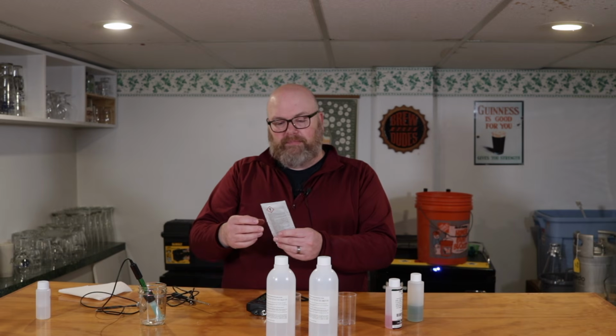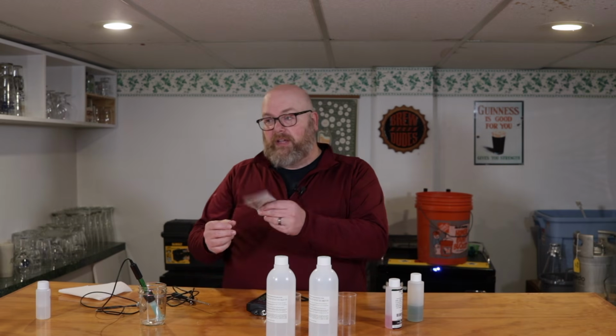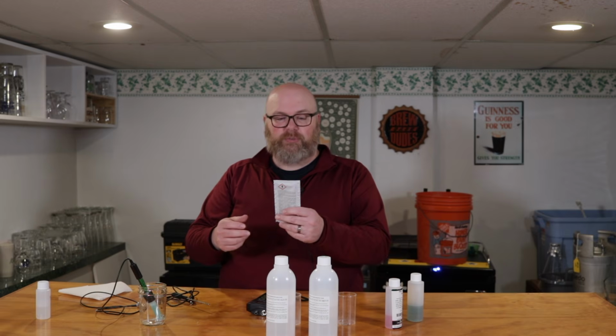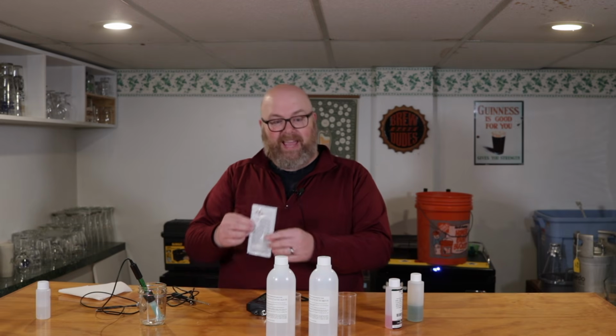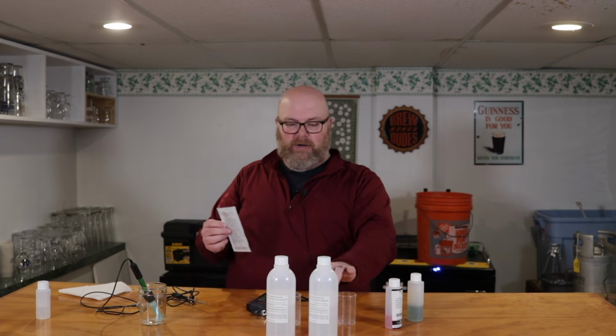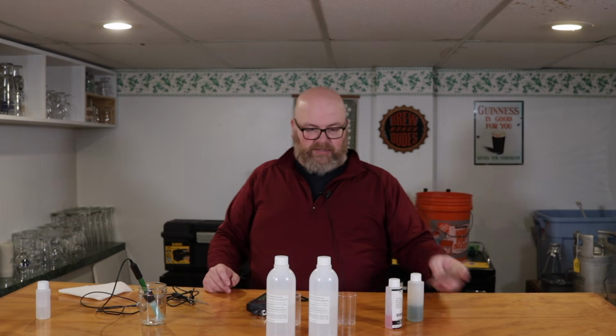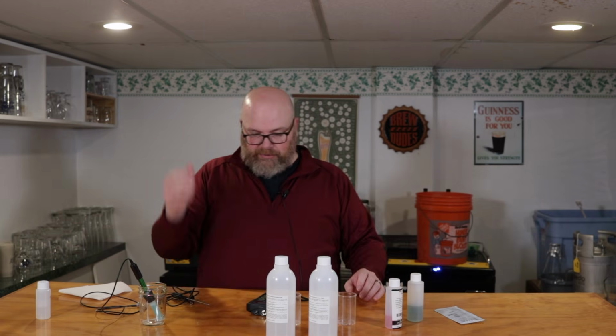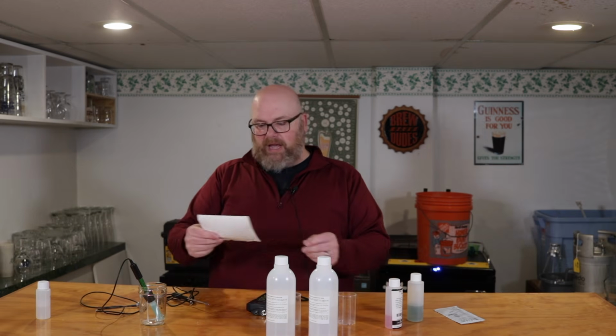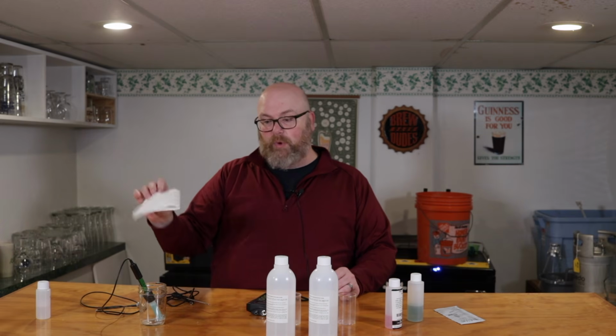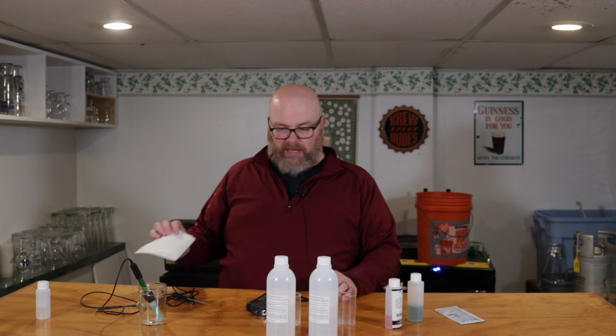So these are really one use only, but they're convenient because they're disposable and they're not super expensive. And they're self-contained. You don't have to worry about having a clean container to do it. So there's that. So you've got your calibration solutions, your probe, your thermometer, the meter. Another thing to have is a paper towel, because you'll want to dab the probe, and you'll see that when I do the calibration.